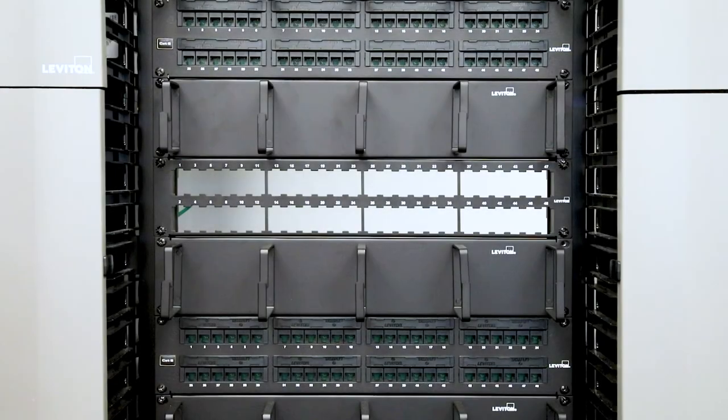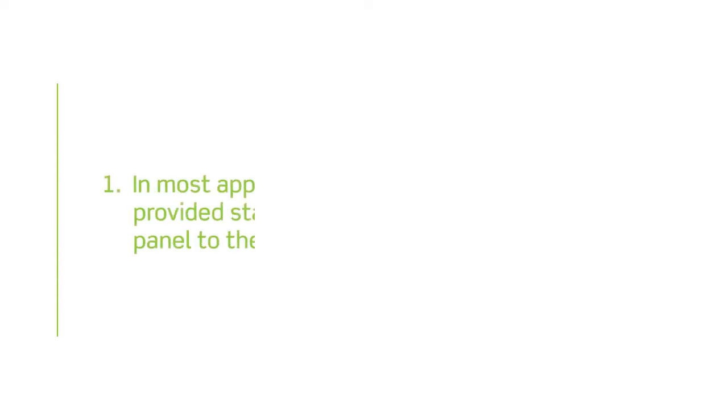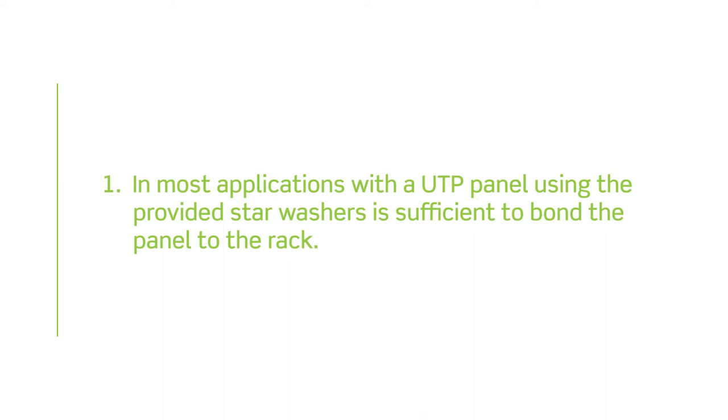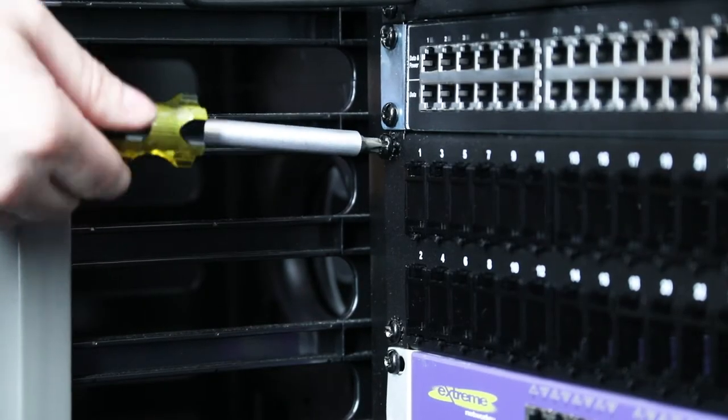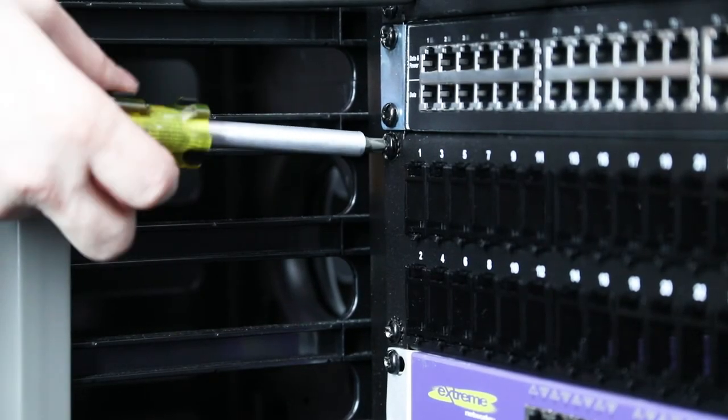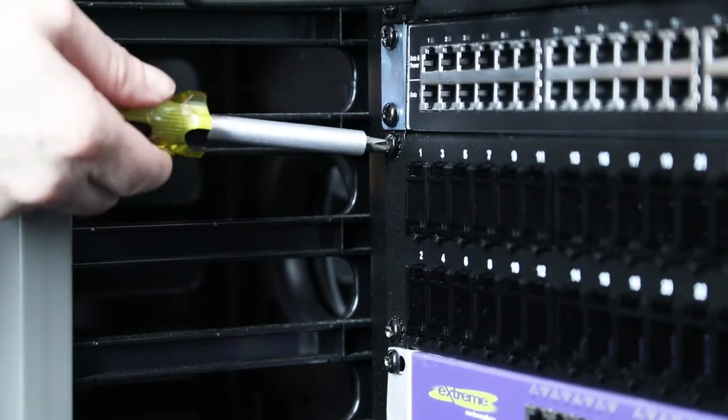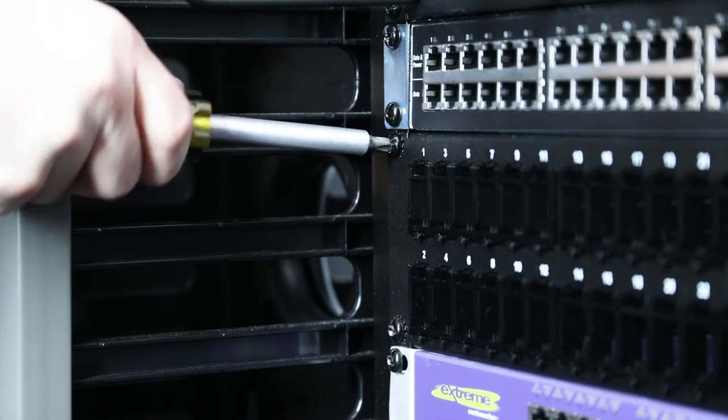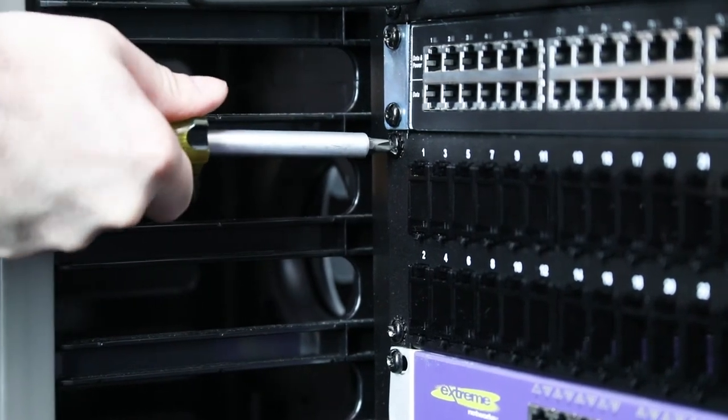First let's get the panel mounted and connect any grounding hardware needed. In most applications with a UTP panel, using the provided star washers is sufficient to bond the panel to the rack. Note washers must be placed between the screw head and the panel and must pierce panel paint to be effective. Use at all four corners.